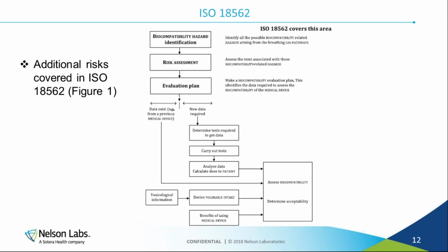And in the last box where it says determine acceptability, that is where your BER would come into play, your biological evaluation report, which would state whether the testing and data supports the safe use of the device for the intended patient contact and patient population.